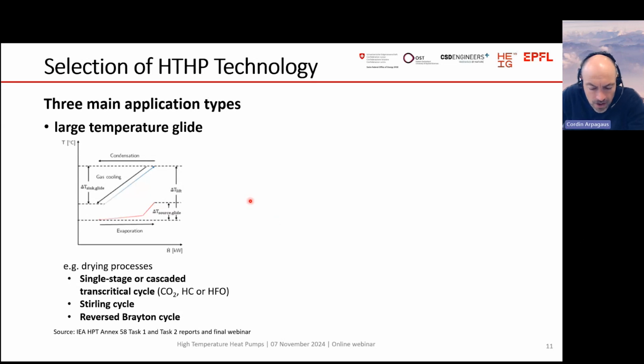When you look at the technology, we have to select a technology that fits the application, the industrial application. So the temperatures are important, the inlet and outlets on heat sink and heat source. And then there are applications with a large temperature glide, so large temperature differences, for example, on the heat sink, for example for drying processes to generate hot air for drying.